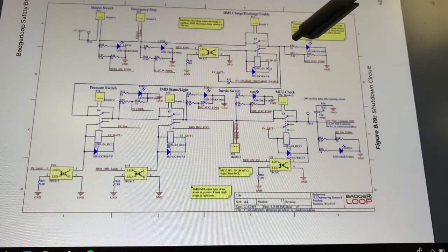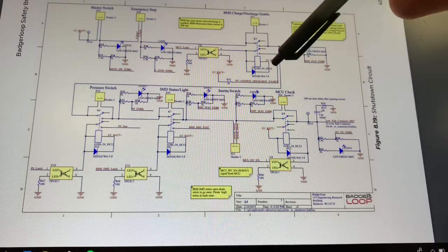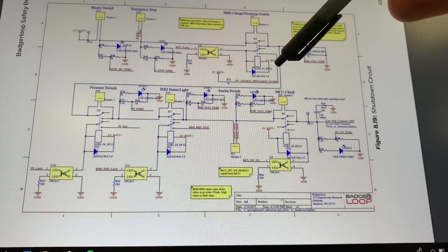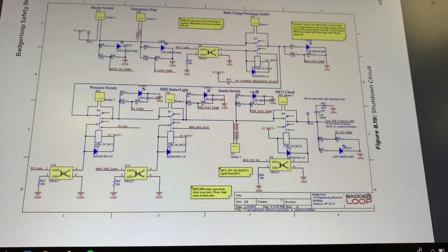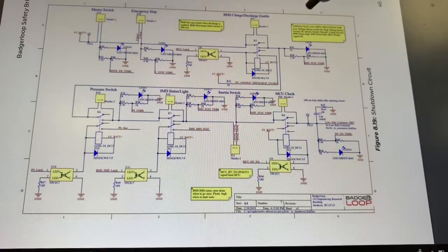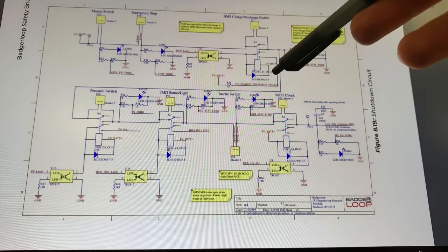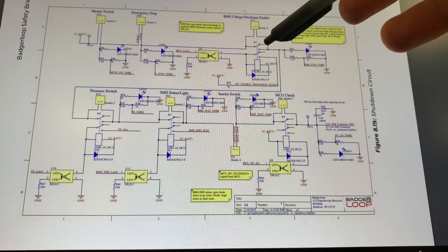Next up looks slightly more complicated, but the gist is this part of the circuit takes in a signal from the battery management system. If the battery management system senses any of the batteries are in an undervoltage state, over temperature state, or we're discharging at too high a rate, it will go to an open drain signal, which will basically open up this relay right here, effectively breaking the circuit.